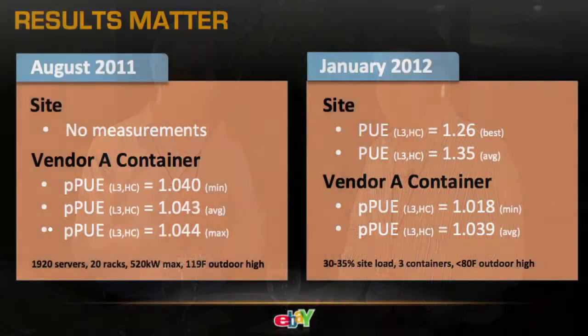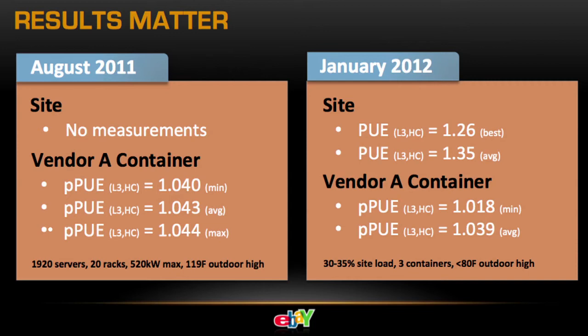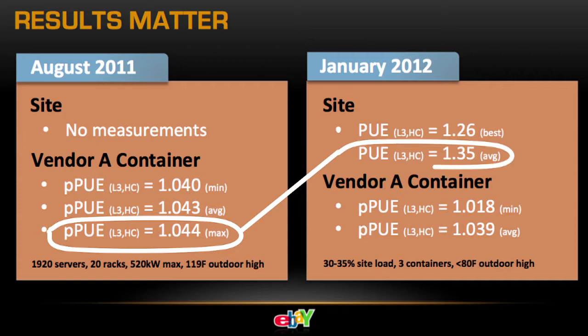It was interesting to watch some of the things I really learned in this, like the container efficiency. The overall container efficiency dropped the site PUE. When we were starting to look at partial PUEs in the containers at 520 kilowatts of load on the roof at 119 Fahrenheit outside, we achieved 1.044, which is incredible. That result actually dropped the site PUE down to an average of 1.35, with a best of 1.26.